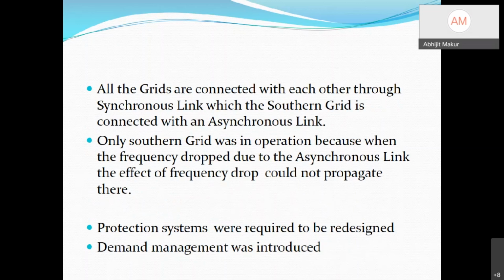Out of this protection system, the concept of demand management came into being. Frequency is one component in the power system that is actually monitored. Whenever the frequency drops to a certain level, the generator goes out of step. So when we find the frequency going down in a grid, it is very necessary to disconnect load, but to disconnect it in such a way as to maintain the generation and at the same time not disturb the system.